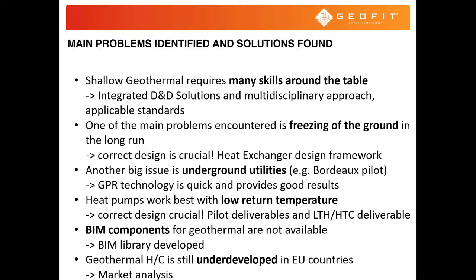Another problem I wasn't aware of, since I was no expert on geothermal - meanwhile I hope I am a little bit more - is freezing of the ground. When you start doing calculations, you realize that as long as you don't dig a lot of boreholes or excavate a lot of earth baskets, you will in the long run reduce the temperature of the ground more and more until it may even freeze, going below zero. This requires special attention, therefore design of the heat exchangers is crucial.